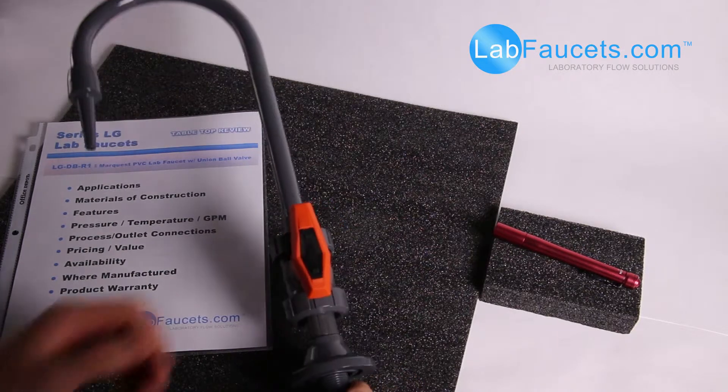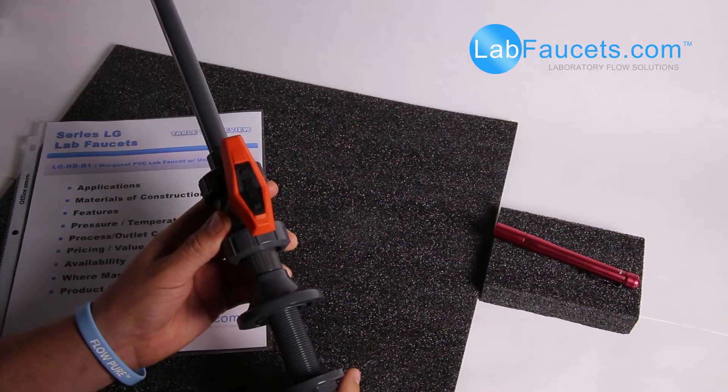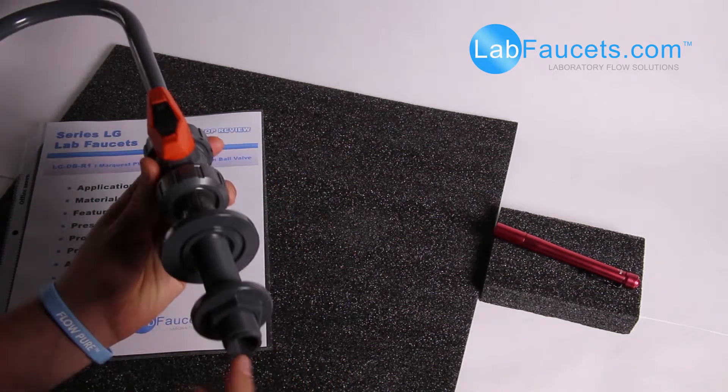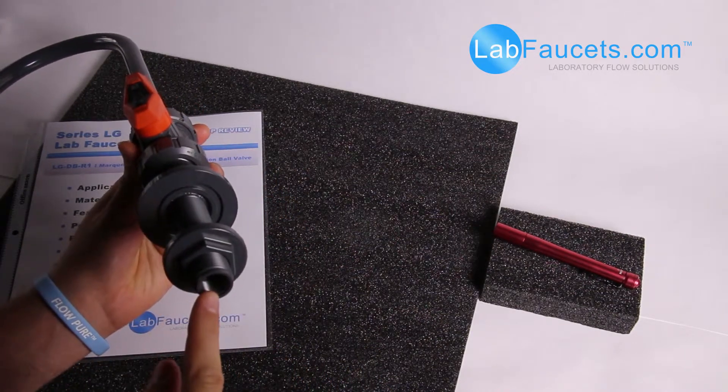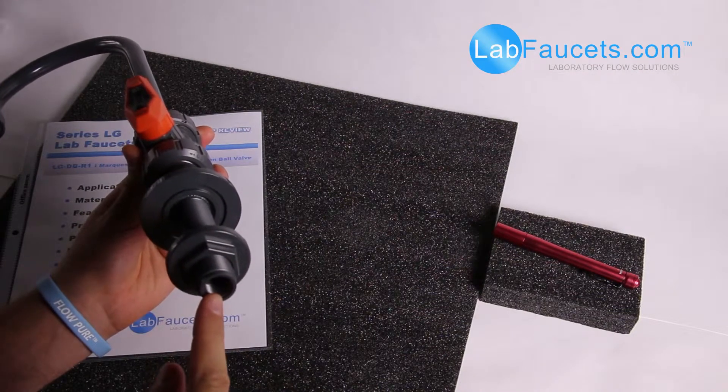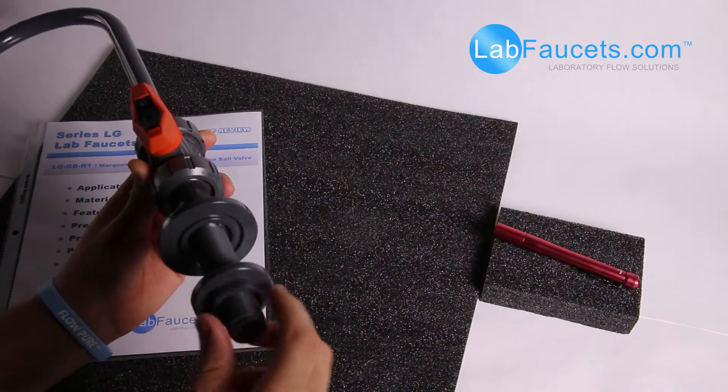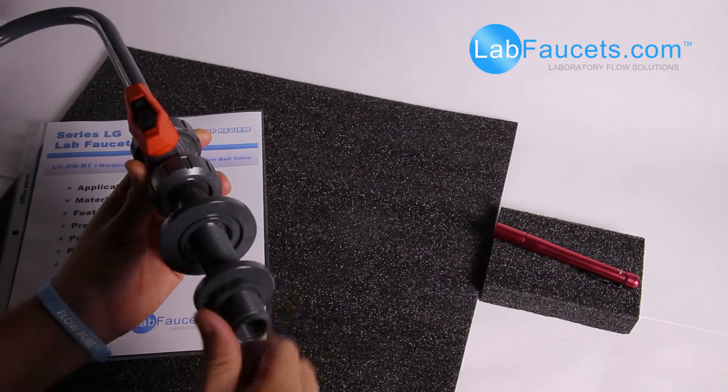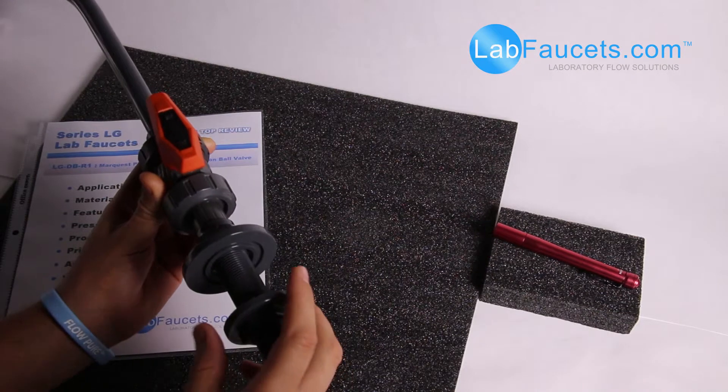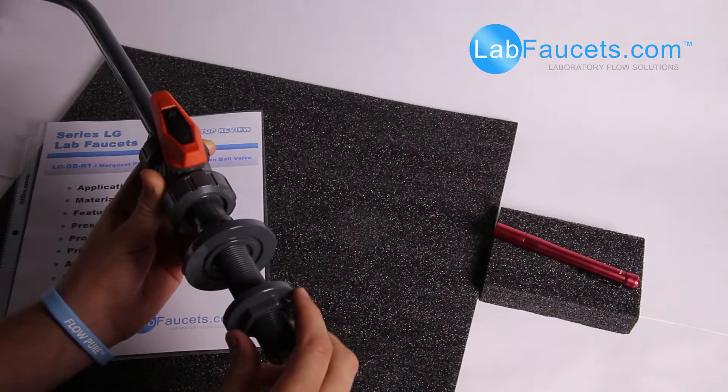The process and outlet connection, as I mentioned earlier, are an internal 3/8 female NPT supply connection. This outer thread here is not a sealing thread, and it's just a mechanical thread for mounting purposes only.